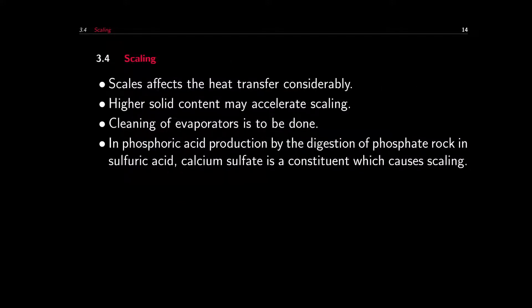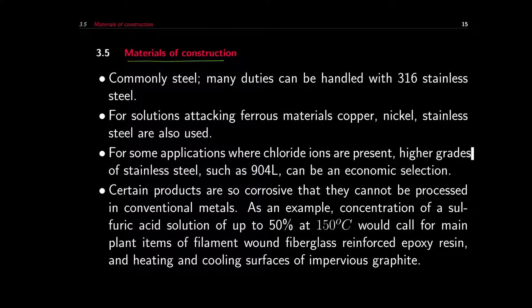Another factor is scaling — scale affects heat transfer considerably, and higher solid content can accelerate the scaling process, so cleaning of the evaporators is needed. For example, in phosphoric acid production by digestion of phosphate rock in sulfuric acid, calcium sulfate is a constituent which causes significant scaling. Material of construction is another factor requiring significant consideration. Commonly steel or 316 stainless steel can be used for many purposes. However, some feeds and products can be detrimental to ferrous materials — for these cases, copper or nickel are used. For applications where chloride ions are present, higher grades of stainless steel such as 904L can also be an economical selection.